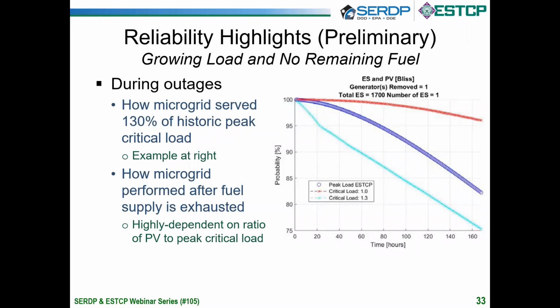Where the storage-enabled microgrid fell on that metric, how long it could protect loads when there's zero diesel fuel on base, depends largely on the ratio of PV capacity and battery energy, megawatt hours, on the base to its critical load. If a base had quite a bit of PV and battery storage relative to its critical load, not surprisingly, it can provide some coverage of critical loads for many hours even without fuel.